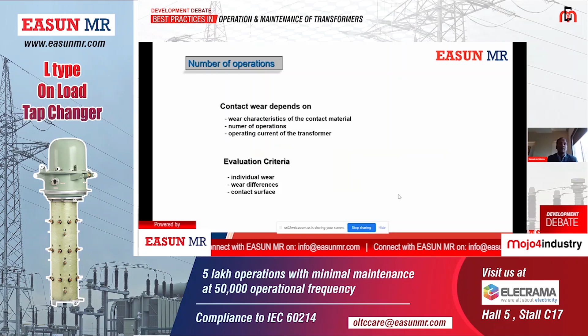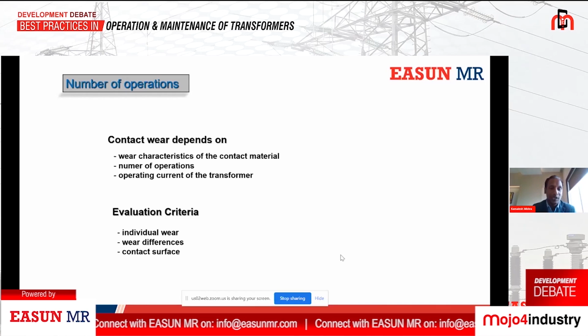It also depends on what the engineer is supposed to check when they go there. Each and every contactor has to be measured with vernier calipers, and they have to check the contact surface so that it does not bounce. This has to be checked very carefully, and it can be checked only by a trained service engineer. We should not forget that, because anybody can say, yes, I am a service engineer, but we should not take risks with the transformer. Transformers cost crores, so we should not allow just anybody to touch your OLTC to do a service. Only use expert service engineers.